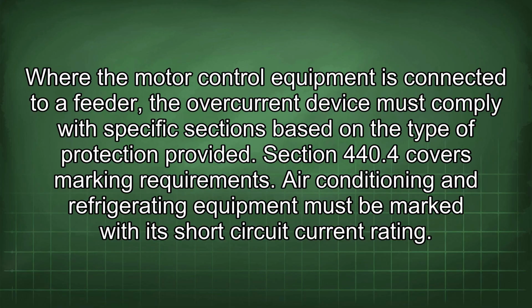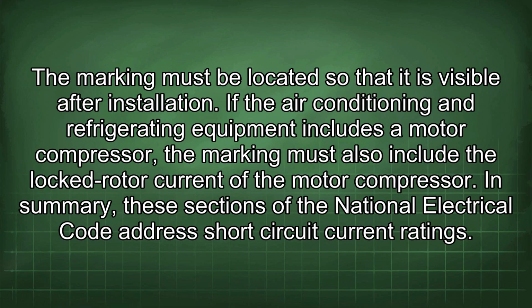Section 440.4 covers marking requirements. Air conditioning and refrigerating equipment must be marked with its short-circuit current rating. The marking must be located so that it is visible after installation. If the air conditioning and refrigerating equipment includes a motor compressor, the marking must also include the locked rotor current of the motor compressor. In summary, these sections of the National Electrical Code address short-circuit current ratings.